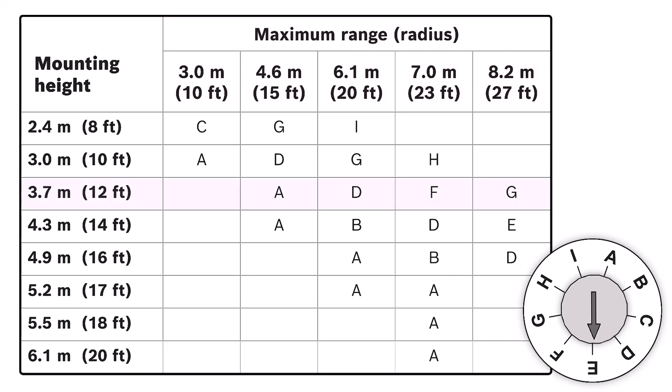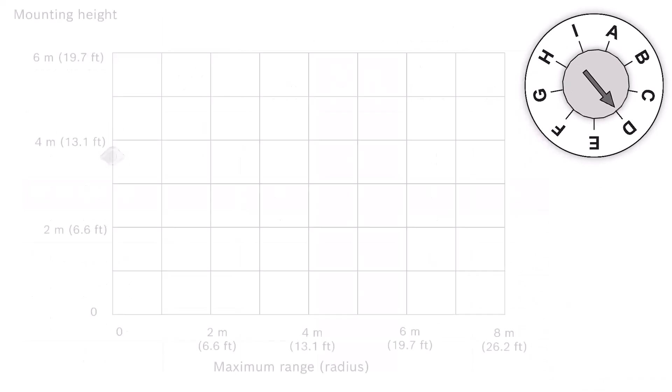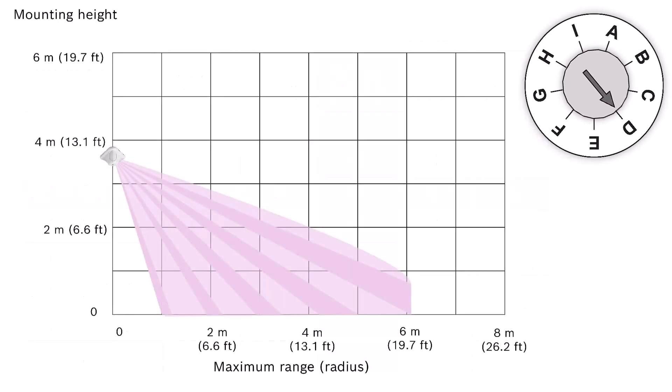For example, if we are mounting the detector at a height of 3.7 meters (12 feet), and we want a radius of 6.1 meters (20 feet), we would set the dial to letter D. This is the detection pattern for this example.